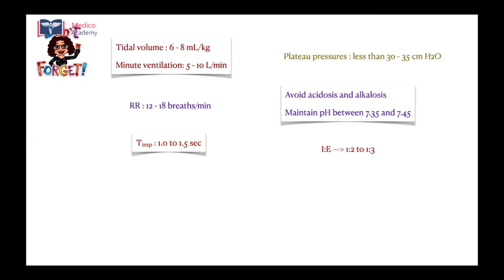So remember, whenever you change the respiratory rate, your inspiratory time is remaining constant, so your expiratory time is getting compromised. So when you change the RR, make it a habit to change or adjust the inspiratory time so that your IE ratio remains between 1:2 and 1:3. The inspiratory flows that can be delivered using your machine are 60 to 200 liters per minute. Adequate would be just 60. But in obstructive airway disease patients, keep flows beyond 100 liters per minute.